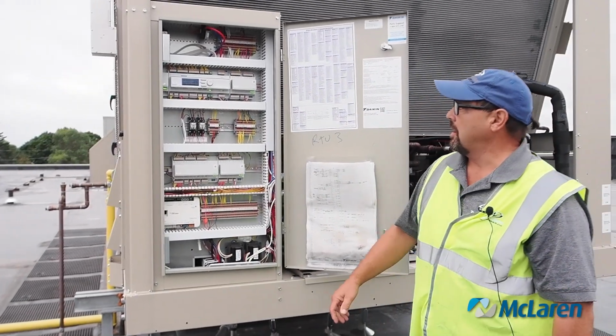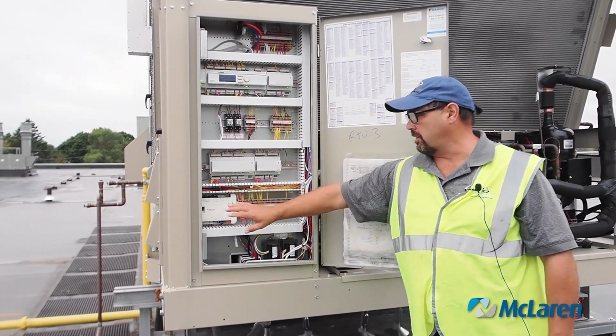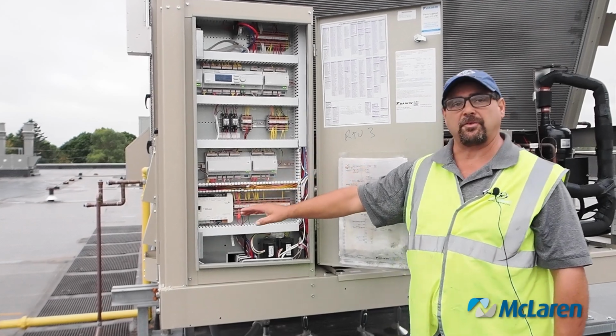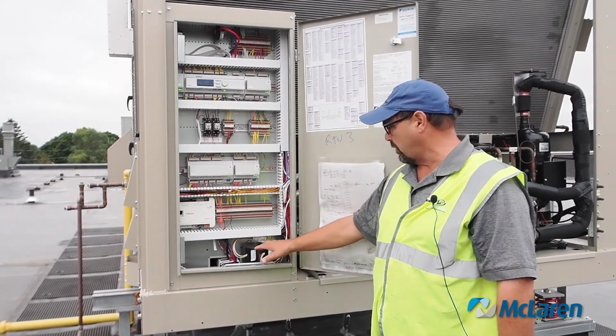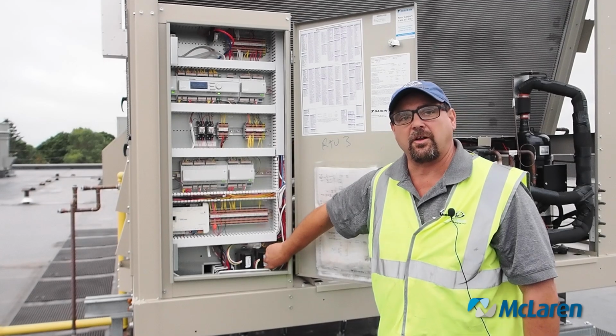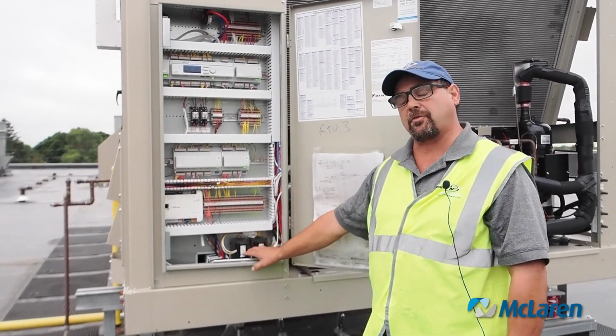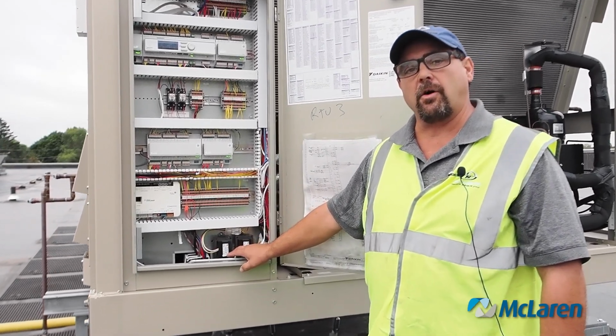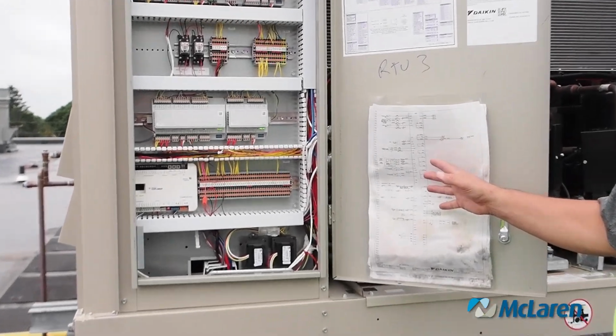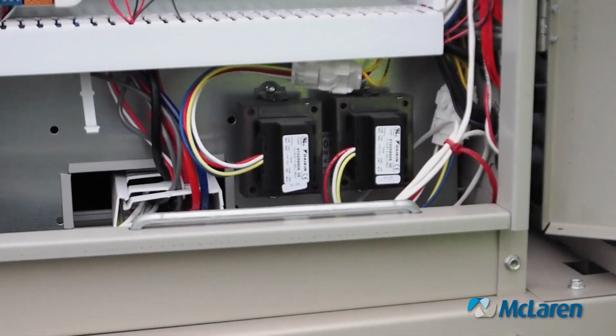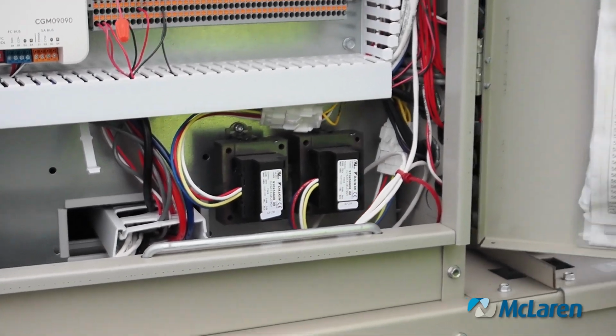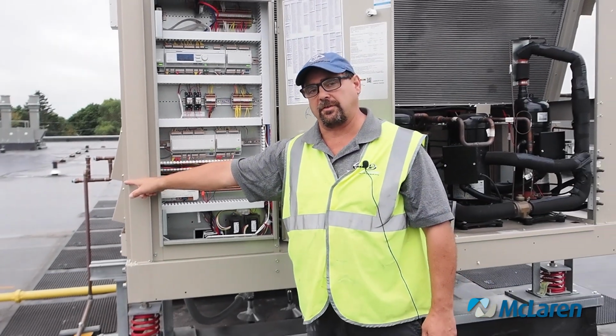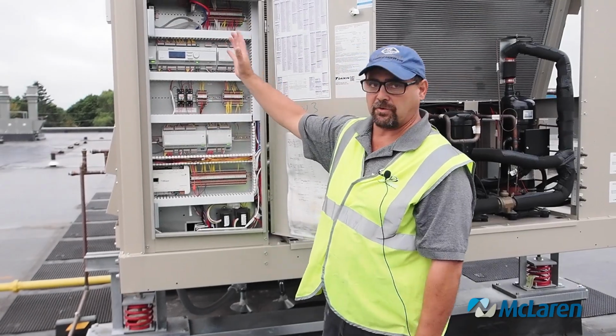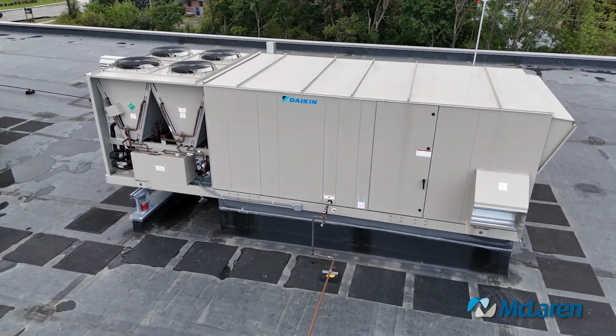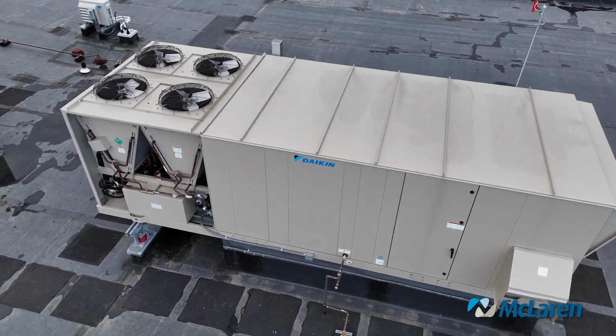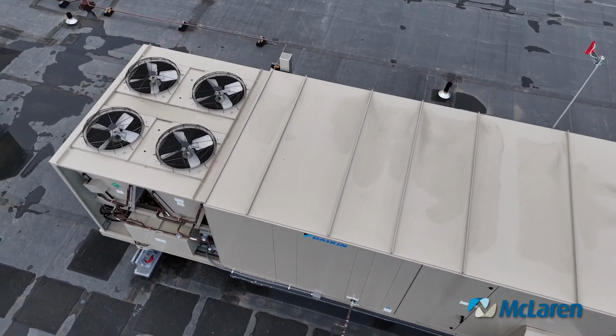Inside this section is all your control components, including the BMS control component, or the building management system control component. You have some transformers here. They do have a resettable fuse on them. If it does trip, please follow up through the print on what might have caused that, what that transformer controls. Once a year, when you turn it off gently here, and then you kill power over at the disconnect and lock out and tag out, you check all your electrical connections in here. Daikin labels all of their wiring, so if you pull out a wire, it'll tell you where it goes.